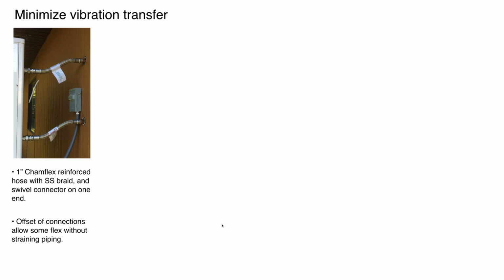Now, we want to keep the system, certainly the indoor portion of the system, as quiet as possible. Anytime you have a compressor, inevitably you get some slight vibration, okay? And I'm showing here a detail. This is an air-to-water heat pump with a couple pieces of reinforced hose. This hose is available from several manufacturers. This happens to be by a company called Chamflex. And what that is, I believe, is an EPDM inner hose with a stainless steel braided liner on it. And one end has a swivel union. The other end, in this case, it's a 1-inch nominal pipe size that just has an FPT connector on it.